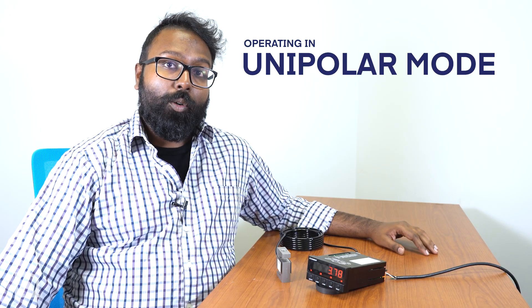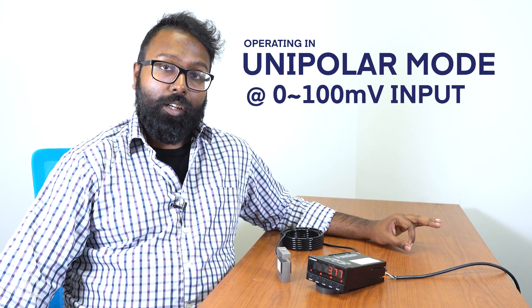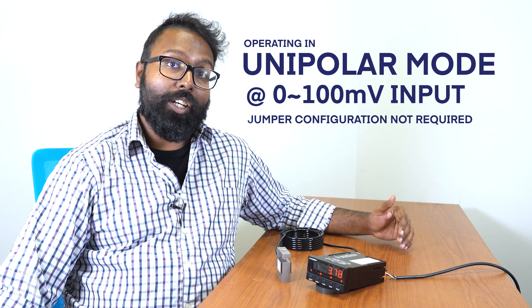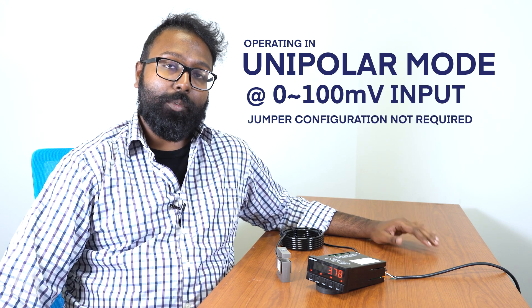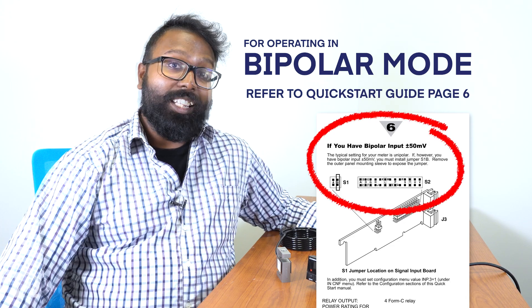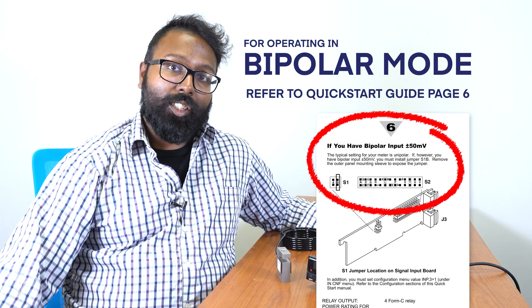Since we're operating in unipolar mode to read 0-100 mV input, there's no need to change any of the jumpers on this meter because when the meter ships out to you, it's set to accept 0-100 mV inputs. If you want to read in bipolar configuration, refer to page 6 of the quick start manual. The link to the quick start is down below in the description of this video.